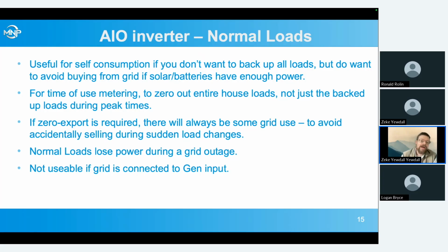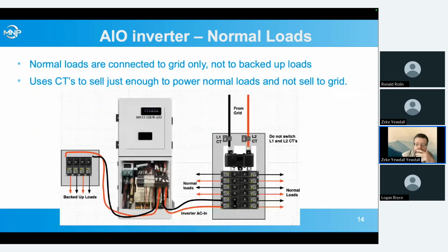Some things to know about this is that if we do have zero export required, the utility is not allowing us to export, we need to set the settings such that there's always some use from the grid. This is to avoid accidentally selling during sudden load changes, because it's selling a certain amount of power into this main loads panel. Say something big in that main loads panel suddenly turns off. It's going to take a second or so for the inverter to respond to that and reduce the amount that it's selling into that panel.